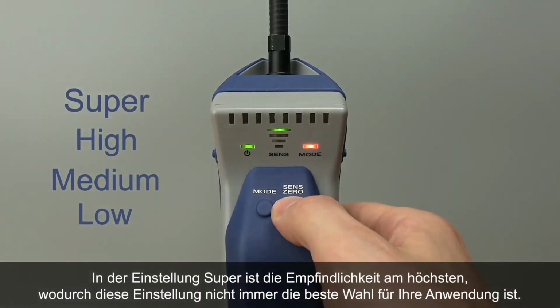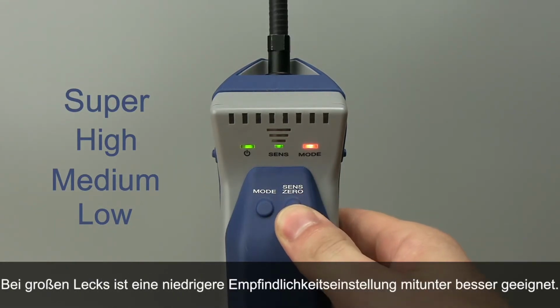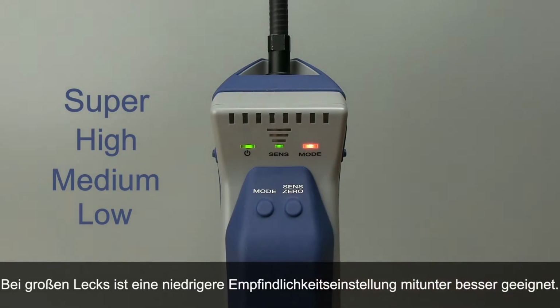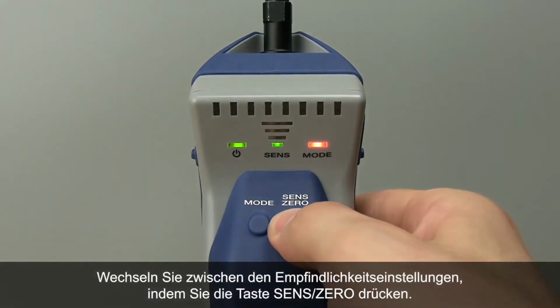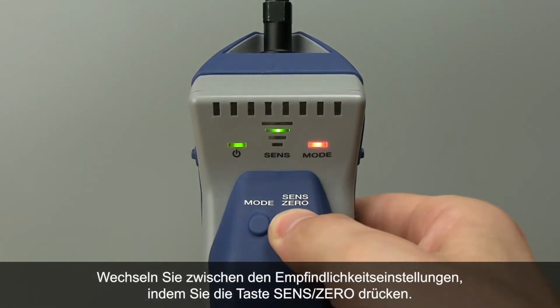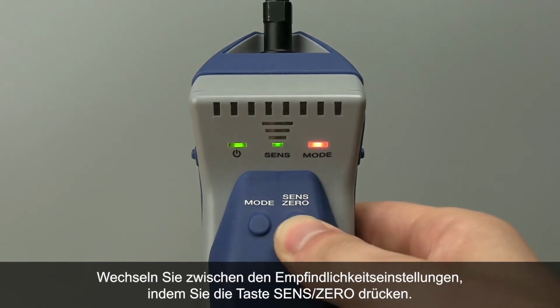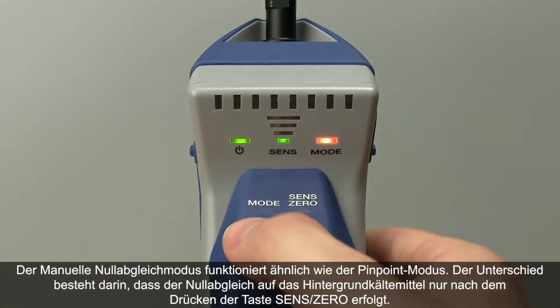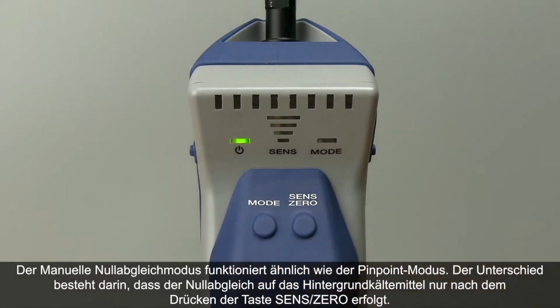While super is the most sensitive, it may not always be the best for your application. For large leaks, a lower sensitivity setting may work best. Toggle between sensitivities by pressing the Sense Zero button. Manual zero mode operates in a similar way to pinpoint mode, except it will only zero to the background refrigerant when you press the Sense Zero button.